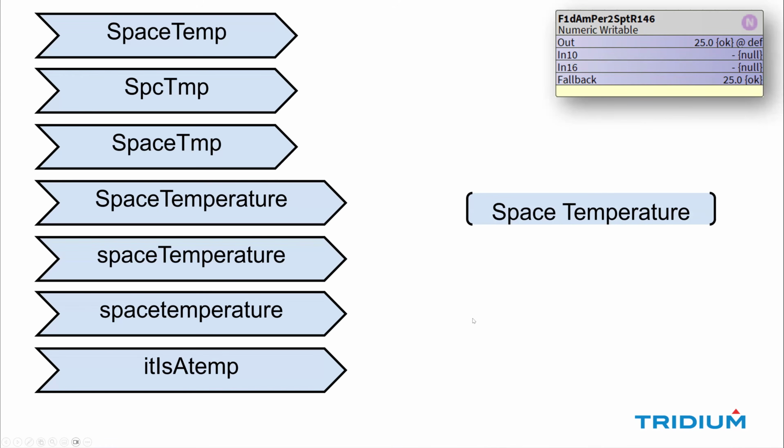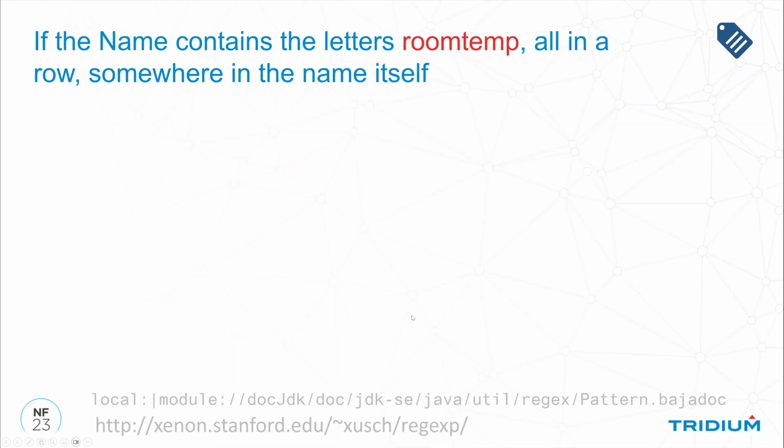I have to know what the naming pattern is, but I can create a rule that tags that data using those different naming conventions that they use. So if I've got a campus and I buy a new property, this is so important because I don't have to think through that when I say I need the space temp tag, I don't have to worry about what it's called. I just get all the ones that are associated with that.